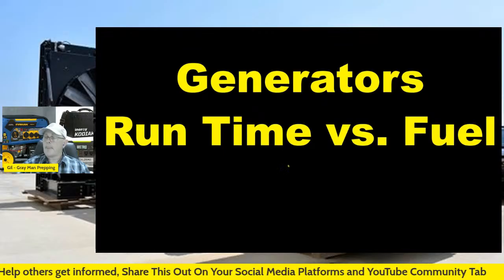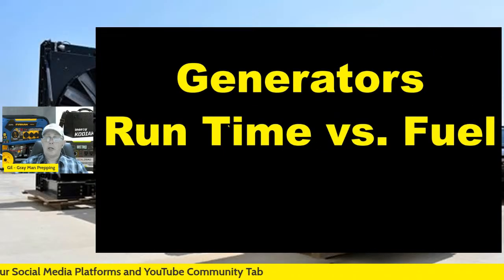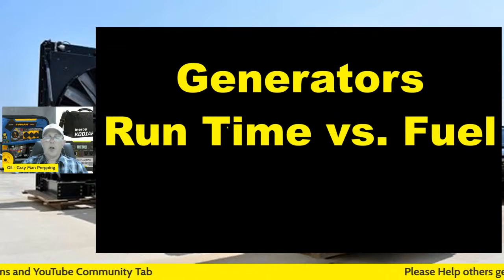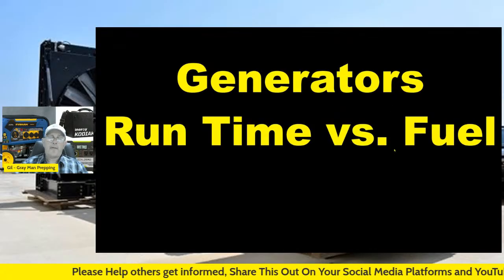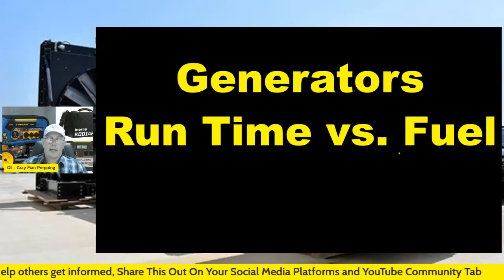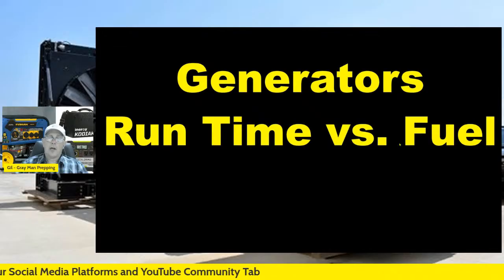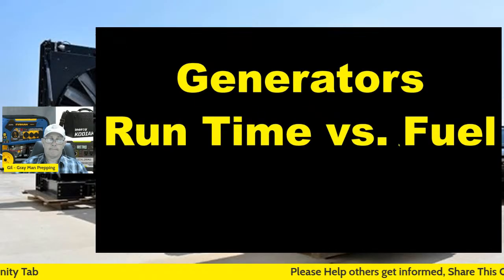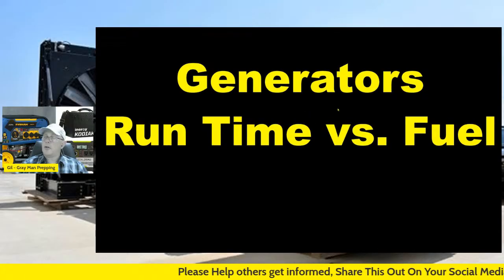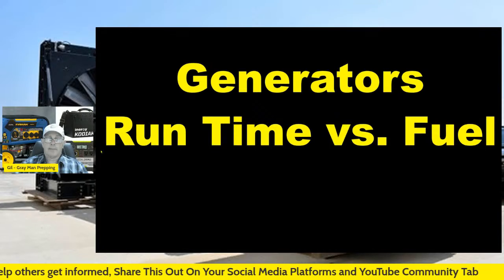Now, one of the things I tell people, if they say, I got a generator, I can power my house, is don't power your house all the time. Unless you happen to have a 5,000 gallon fuel tank sitting out back, don't run it all the time. Plus, if you run it all the time, you can only run it for 50 hours before it needs to be serviced. So that's the other thing. You've got to track the hours you're running your generator. At 50 hours, they need to be serviced.